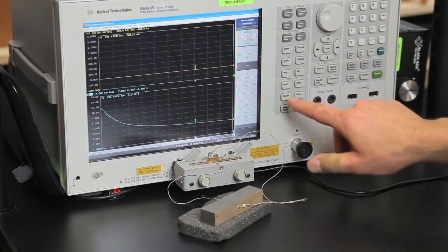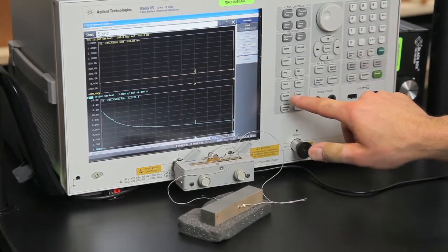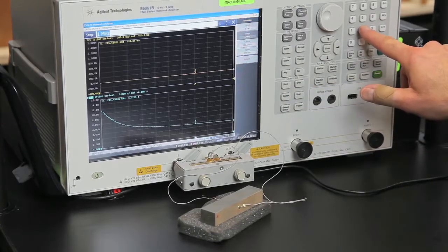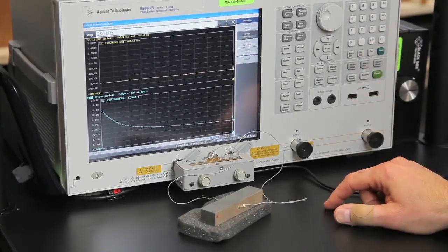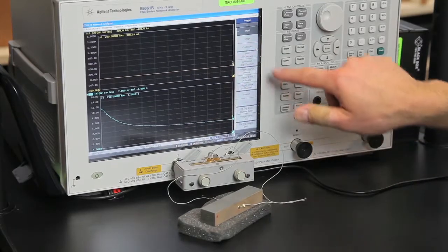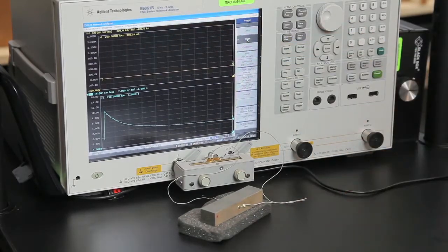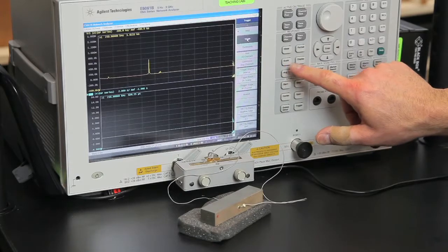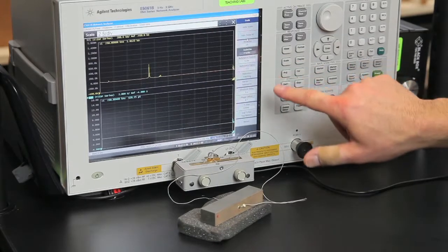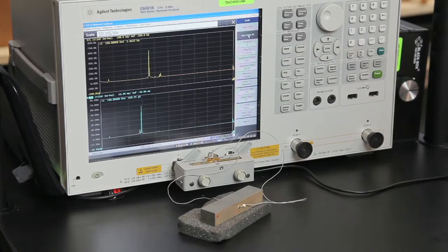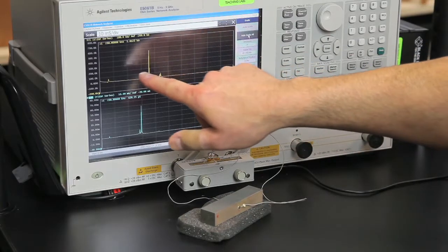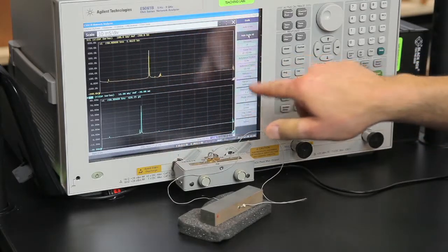I'm going to change my start frequency to 5 kHz and my stop frequency to 250 kHz. Once the sweep is done, I'll do an auto scale by hitting scale and clicking auto scale all. Here you can see the impedance curve and the complex admittance curve.